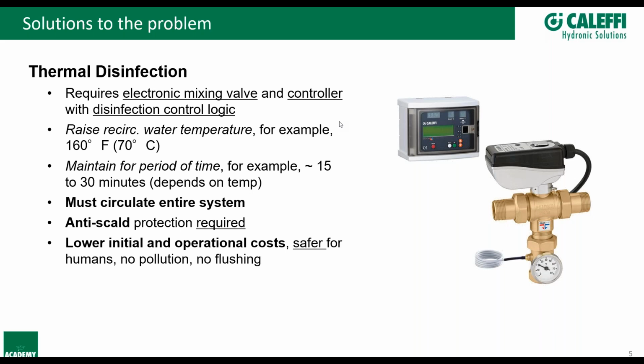With our valve, we do have the ability to handle pressure up to 230, but the normal max working pressure for the dynamic or moving capabilities of the valve is 150 psi. So if you're looking at large high-rise buildings, that's something you need to take into account. If you're doing all your domestic hot water heating at a suite on the roof, it's not a problem because your pressure is much lower. But if you're doing everything from the bottom of the building, that's something you need to address. There are very few valves out there that can handle those incredibly high pressures - that's a very different market. But we can definitely handle the mid-rises, and if you're doing high-rises, you just need to make sure you're below that 150.